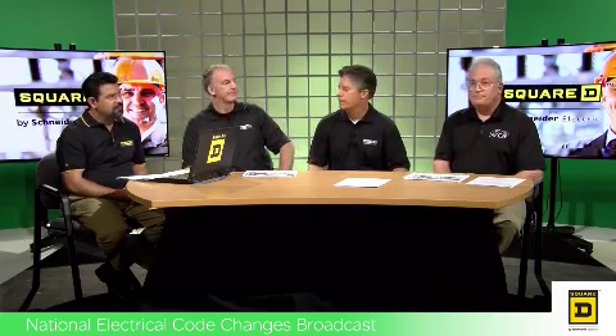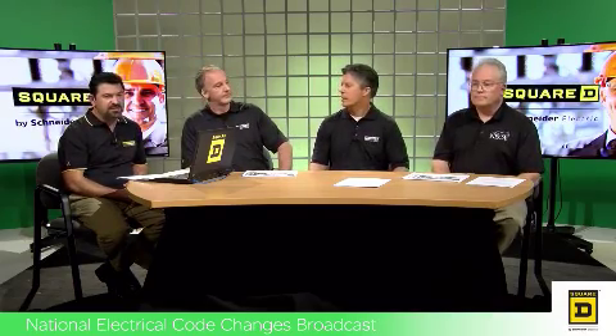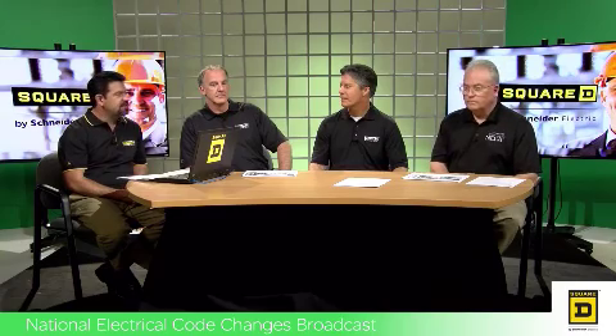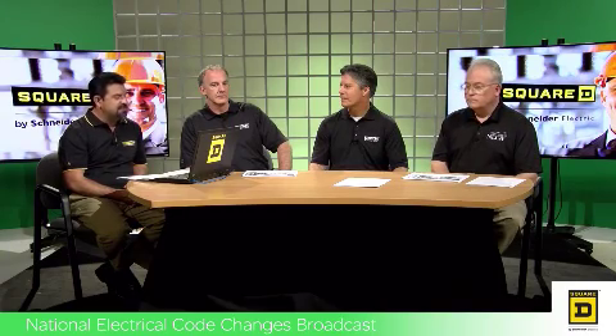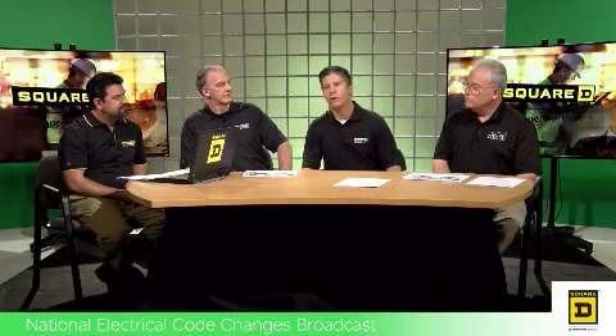Absolutely. Good. So Chad, next one is section 220.12, the exceptions around the lighting loads and for specified occupancies. Great, thanks, Phil. So Article 220 covers your load calculations for your buildings. And we had an exception in the 2014 NEC that really dealt with an adopted energy code where you could use the exception there to use power monitoring with alarms.